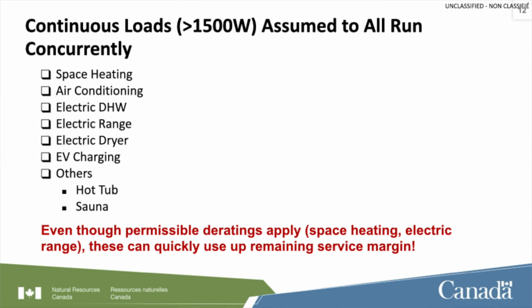What about a secondary suite involved? Well, we're not even going there, because now you're changing occupant loads as well, so your base load will change. Now you basically have 2 dwellings, which really throws things off - twice as much heating, twice as much air conditioning, twice as much of everything. It's double the fun. Even though permissible deratings apply, the space heating and stuff can quickly eat up this margin.